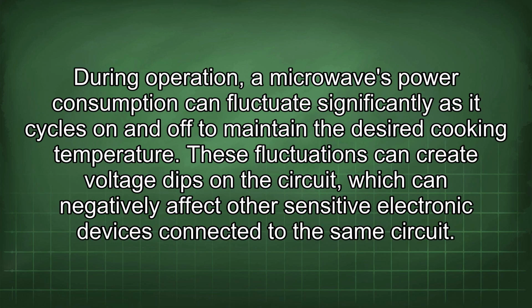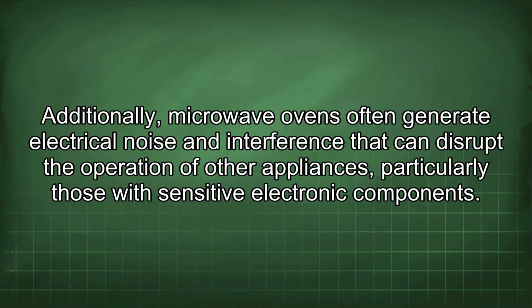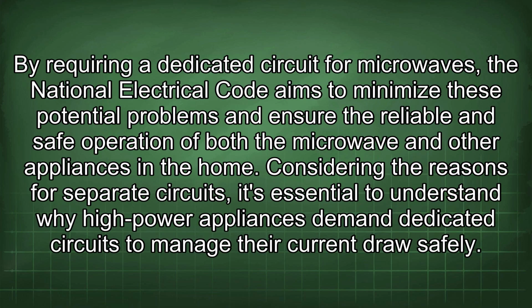During operation, a microwave's power consumption can fluctuate significantly as it cycles on and off to maintain the desired cooking temperature. These fluctuations can create voltage dips in the circuit, which can negatively affect other sensitive electronic devices connected to the same circuit. Additionally, microwave ovens often generate electrical noise and interference that can disrupt the operation of other appliances, particularly those with sensitive electronic components. By requiring a dedicated circuit for microwaves, the National Electrical Code aims to minimize these potential problems and ensure the reliable and safe operation of both the microwave and other appliances in the home.